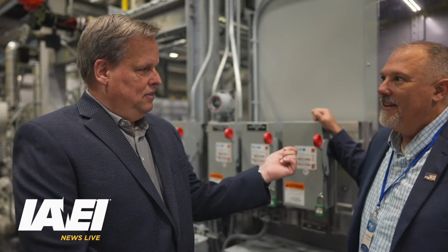Now, here's the other good one. Up is on, down is off. Okay. Then I read this: single throw knife switches shall be placed so that gravity will not tend to close them. How would gravity close this if up is on, closed, and down is off? Yeah, that's why it's made that way. There's another requirement, and not all switches are required to be off and on in those positions. Double throw, yep. But this is single throw knife switches, shall be placed so that gravity will not close them.